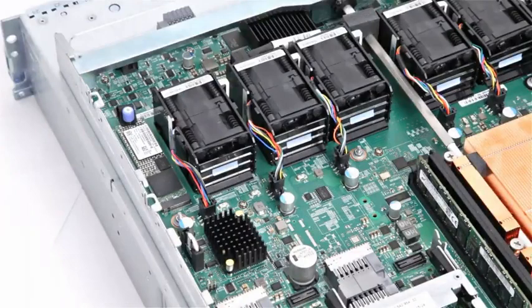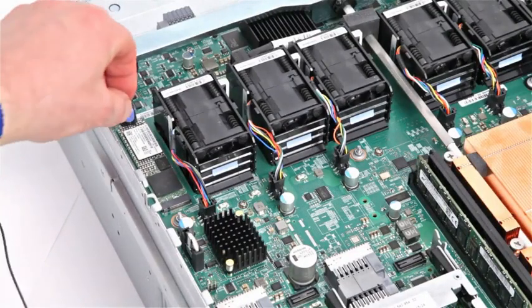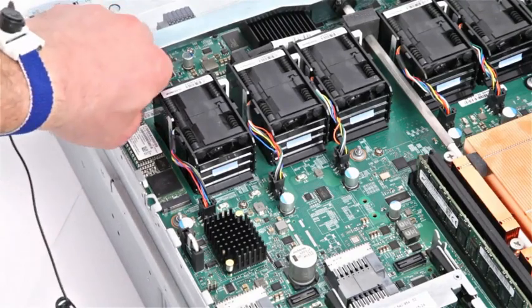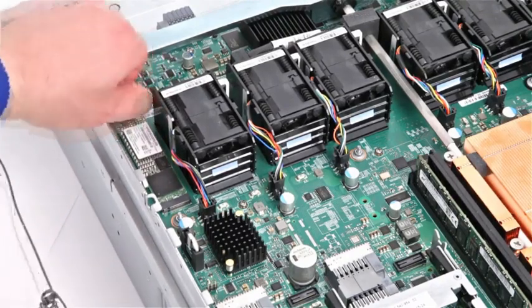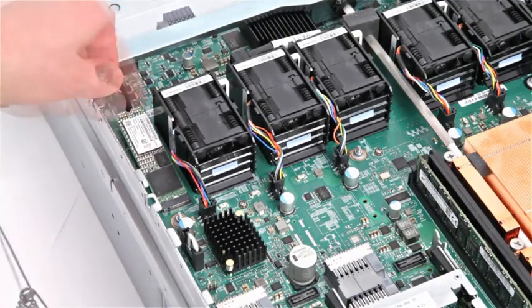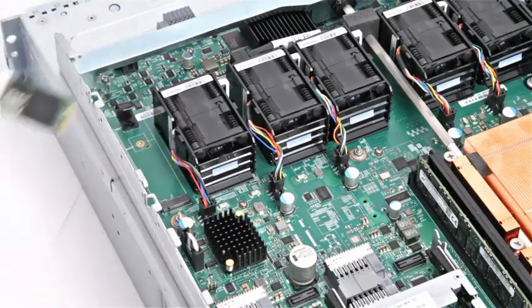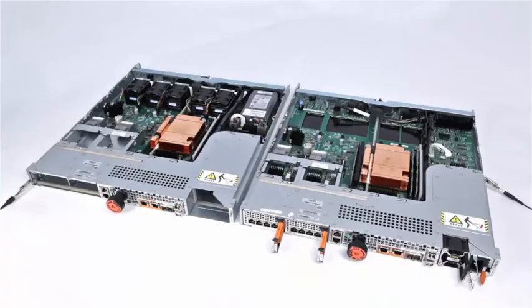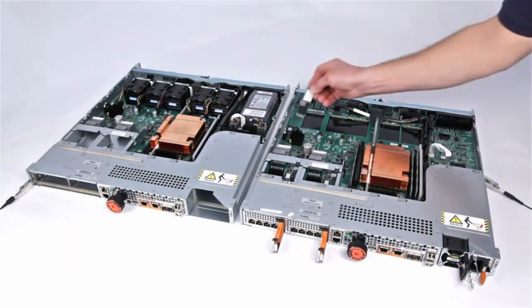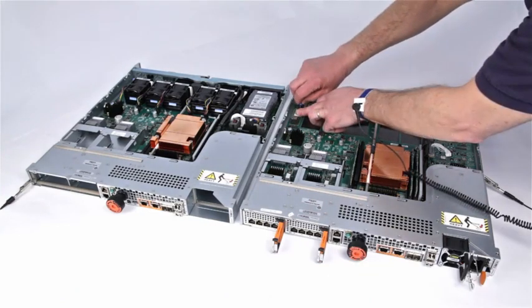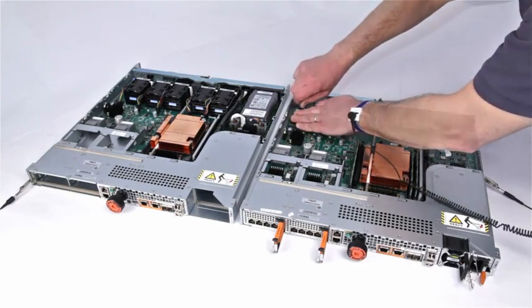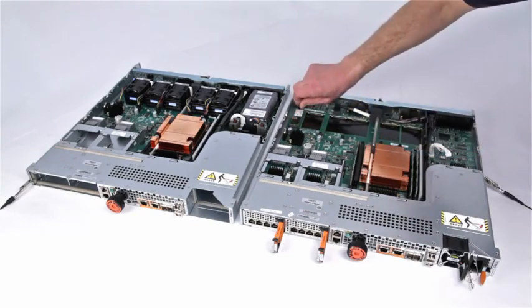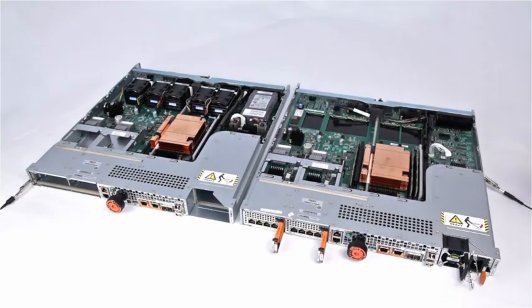Locate the internal SSD, also known as an M.2 SATA board, and rotate the retaining knob counterclockwise until it is free from the mounting stud. Lift the end of the SATA board at a slight angle and then remove it completely from the slot. Insert the terminal end of the SATA board into the slot on the replacement SP motherboard. Place the latch retaining screw into the mounting hole and secure the SATA board to the motherboard by turning the screw clockwise.